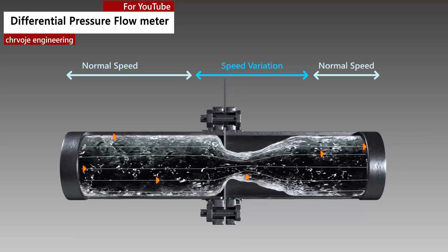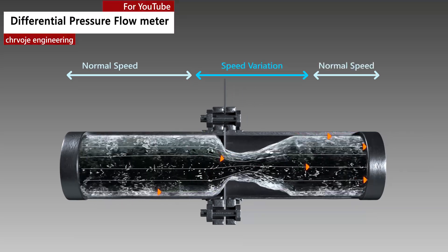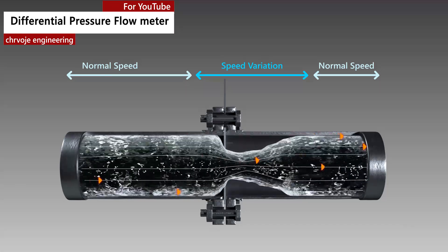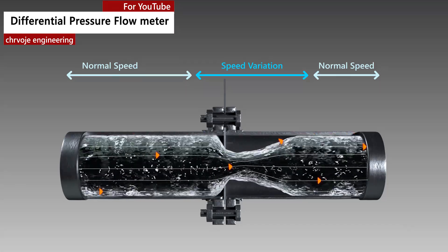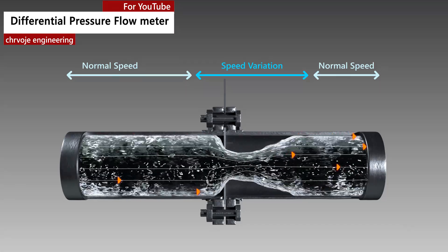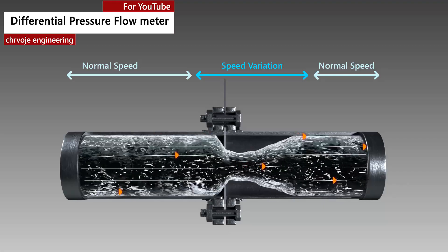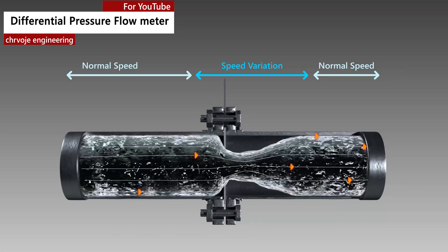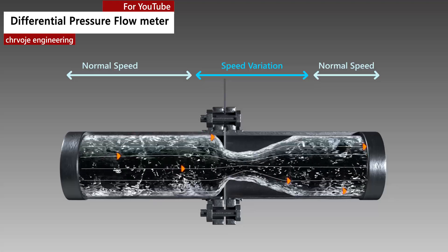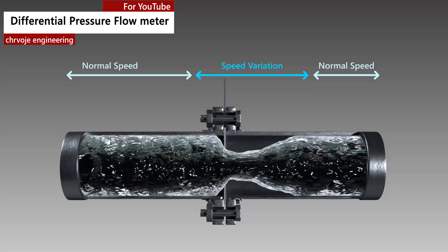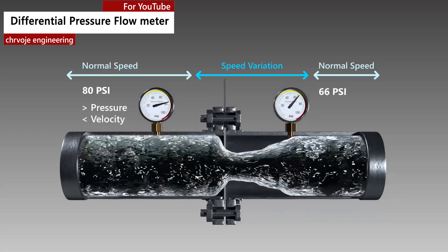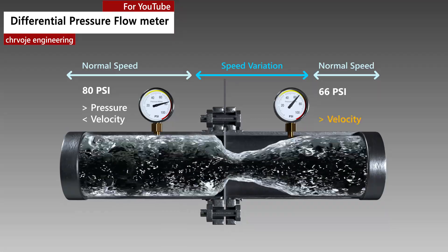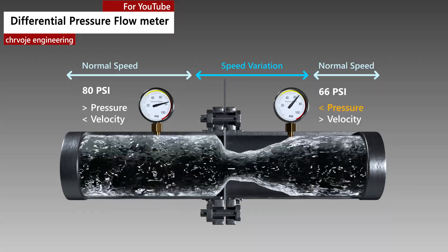According to the laws of conservation of energy, the fluid entering the pipe must equal the mass leaving the pipe during the same period of time. The velocity of the fluid leaving the orifice is greater than the velocity of the fluid entering the orifice plate. Applying Bernoulli's principle, the increased fluid velocity results in a decrease in pressure.